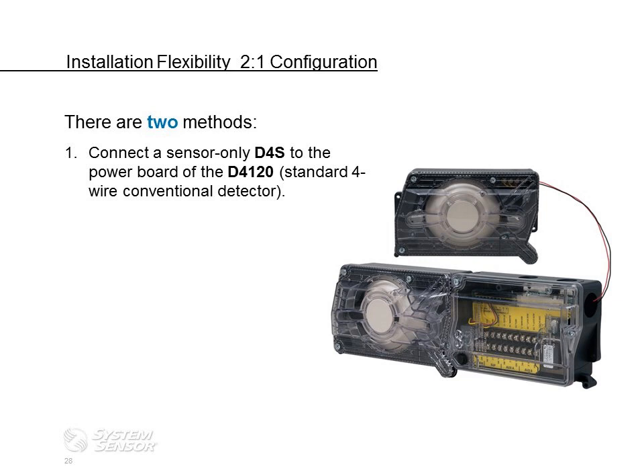And what that 2-to-1 configuration actually means is we will allow you to control, monitor, and test and reset two smoke detector heads with one control board and one remote test accessory. Why is that important? It can be a substantial cost savings if you're in a bid situation or in an application where you have to cover both supply and return because of the size of the unit or the local code requirements. This will allow you to do that.